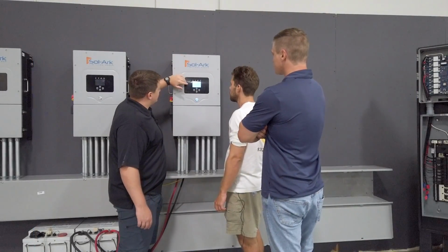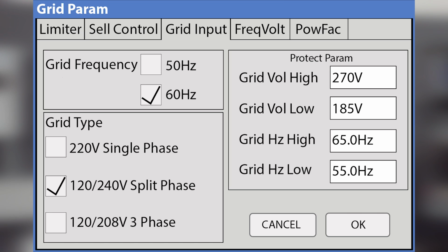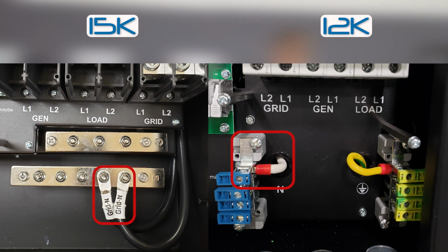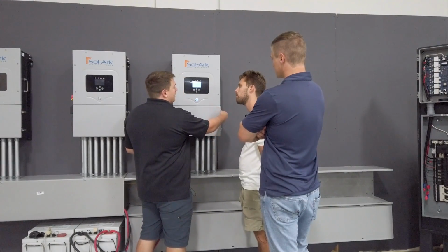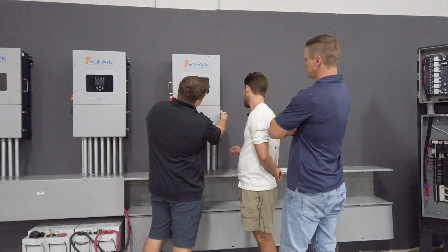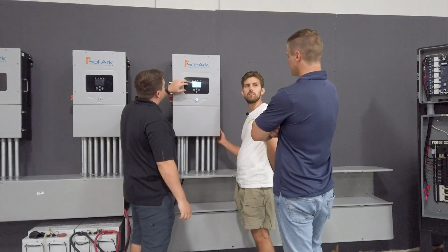We have 3 options here. As we already went over, you can do the 3-phase settings. Default is 120/240 split phase, and then you can also do 220 single phase. If you're going to do that in one of your installs, please make sure that you remove the system neutral reference. This has to come out if you're going to program the Sol-Ark to 220 single phase, every time. So clamp that down.